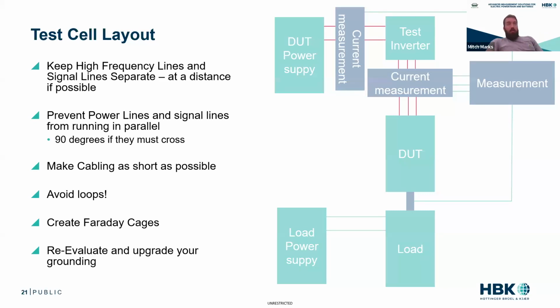Distance is important. We want to prevent power lines and signal lines from running in parallel. You don't want your CAN bus running right along your high current measurement, or your measurement cables running along your high current measurement. And if these high frequency, high power lines and measurement lines must interact, you want them to cross at 90 degrees.